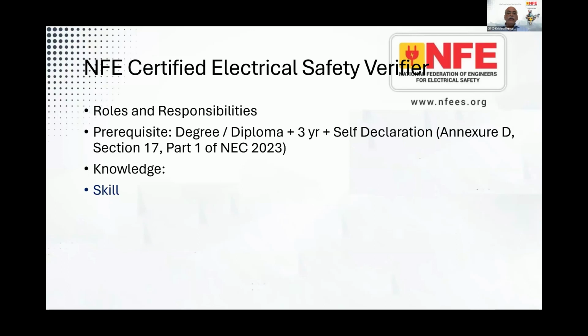Before commissioning, that is before power supply is given, we do initial verification before the installation is placed in service. This is also done after any major modification. If you just add, say, one more light point on an existing circuit, verification is not required. But if an existing circuit is modified, then verification is again required.